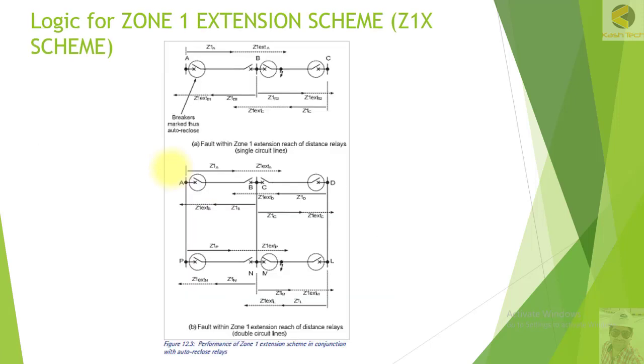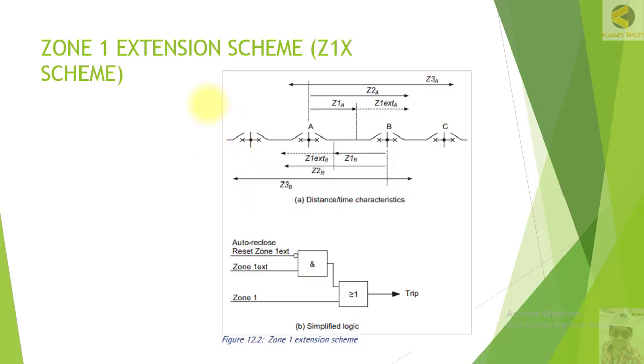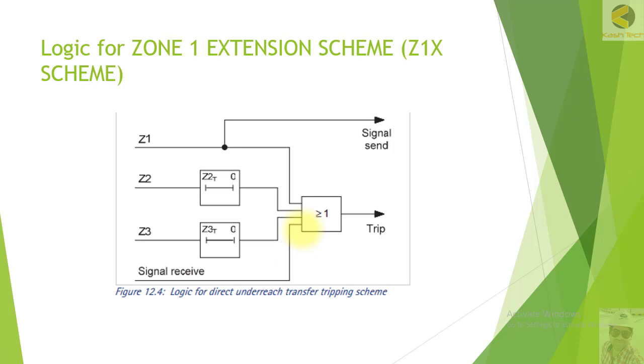This diagram shows Station A and Station B: normal Zone 1A is up to 80% and the extension zone is up to 120%. Similarly for Station B, Zone 1 is 80% and extension is 120%. The trip logic shows that if there is a fault in Zone 1, tripping is immediate; and if there is a fault in Zone 1 extension with auto-reclose reset available, tripping is also instantaneous. This is the simplified logic for Zone 1 extension.